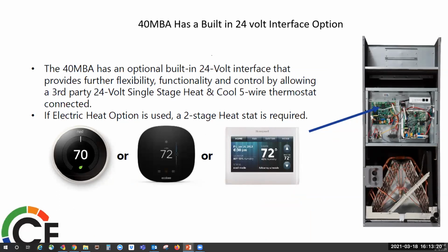When using the 24 volt, you can use the 24 volt interface. You can use a heat cool thermostat. If you have the option of electric heat, 2-stage heat and single stage cooling thermostat, 5-wire. So you can use pretty much any stat with these, because the control of the 4-way valve is all in the algorithms of the 24 volt interface kit.